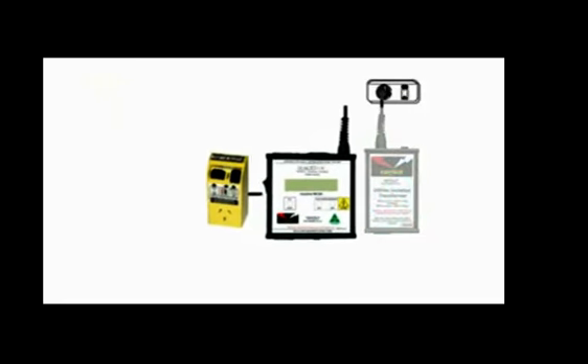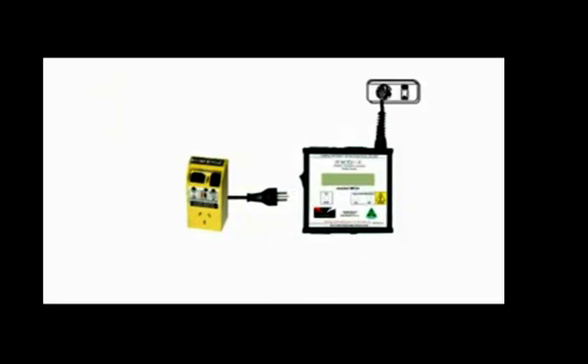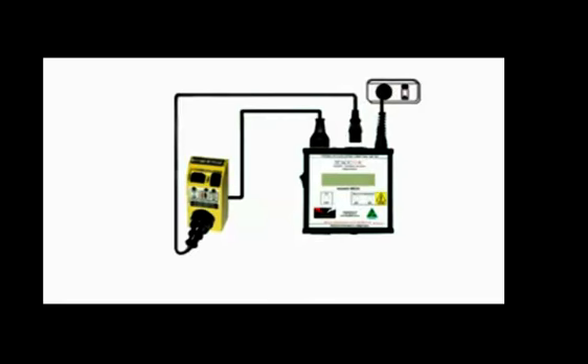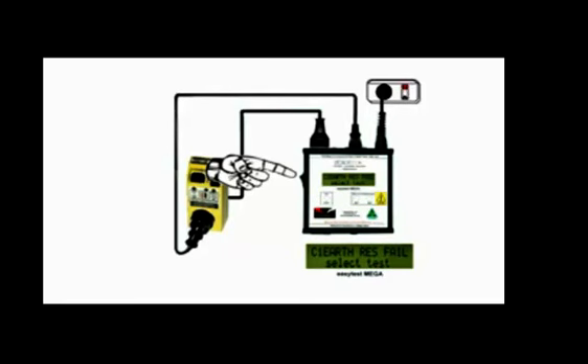The RCD we're about to test is a residual current device safety switch, but it's also an extension lead, and the Mega lets us test it as an extension lead. So plug it into the top of the Mega, and we'll use the IEC patch lead to complete the circuit. Switch it on and select Portable Appliance Test Mode, and instantaneously the EASYTEST Mega performs all the tests for extension leads simultaneously. We appear to have a failure, but some RCDs switch off when the power goes off.